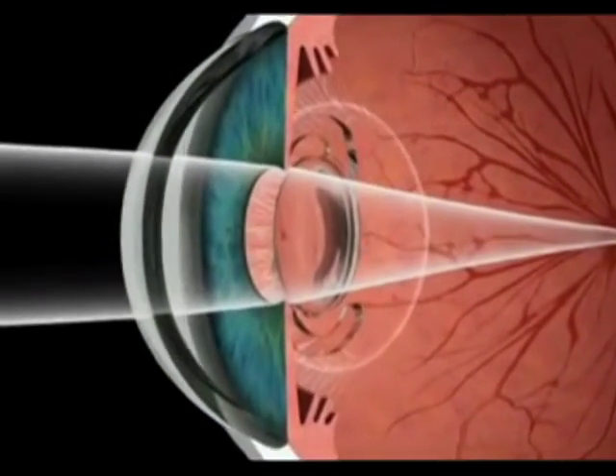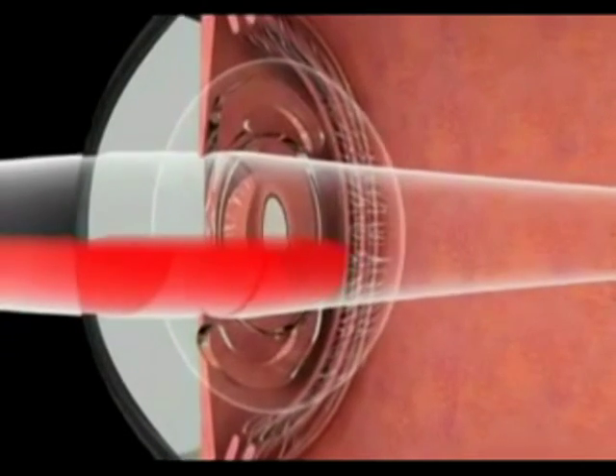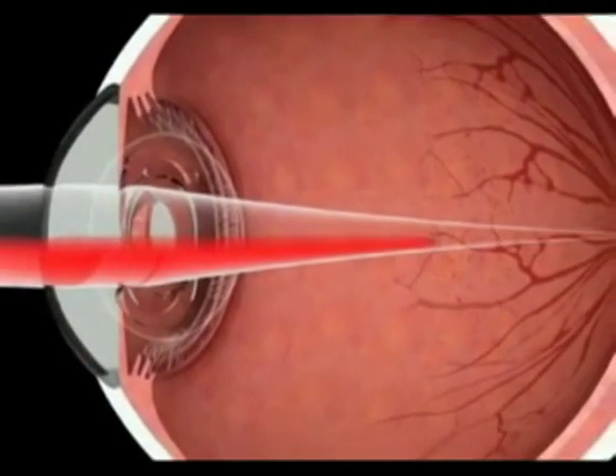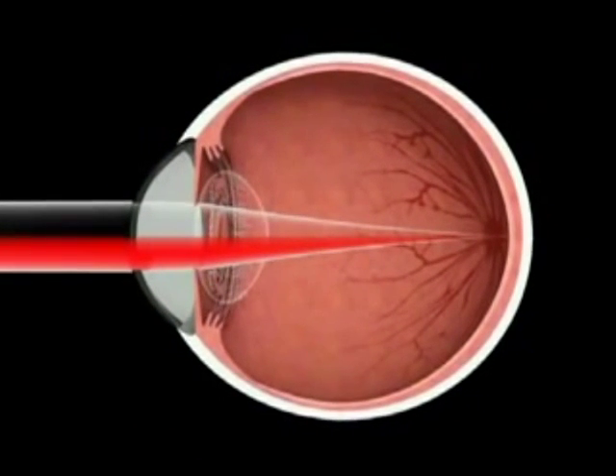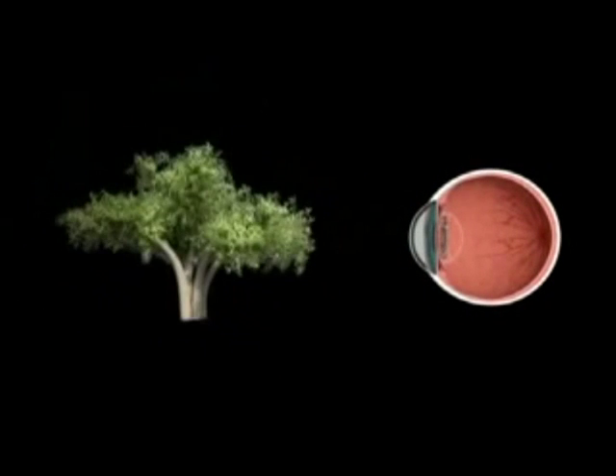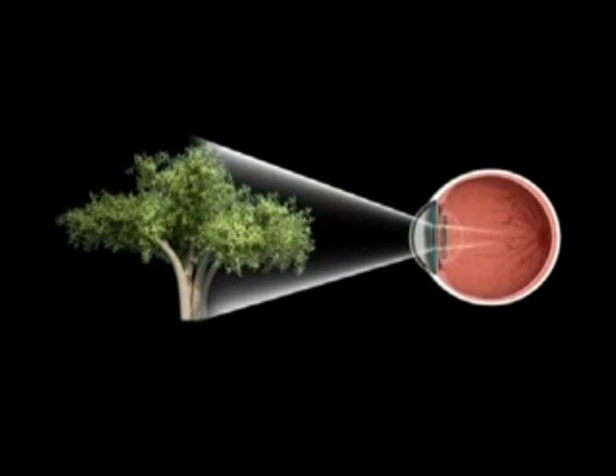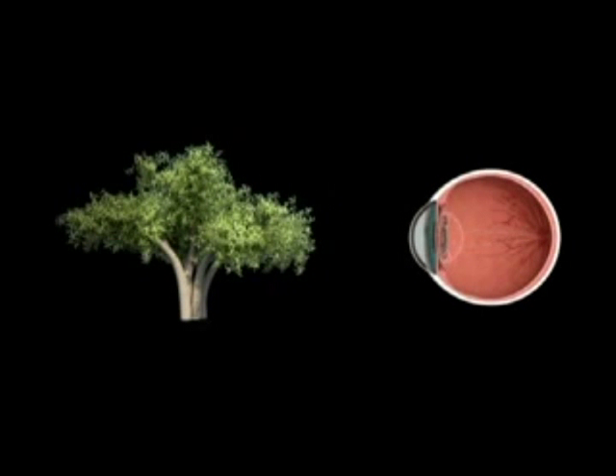When the light hits the transition area in the embedded sector, this will be reflected away from the optical axis. This prevents any superposition of interference diffraction, normally caused by curvature variations on optical surfaces. This will result in a minor loss of light intensity, and at the same time, a significantly improved contrast sensitivity. No ghost or double images should be propagated, and significantly less glare and halo effects should appear.